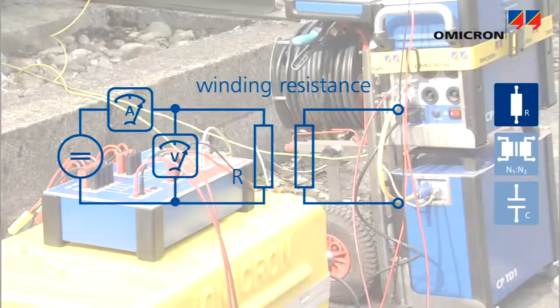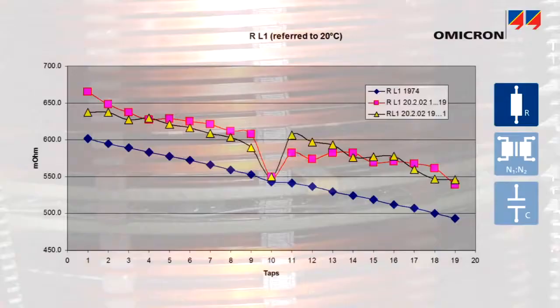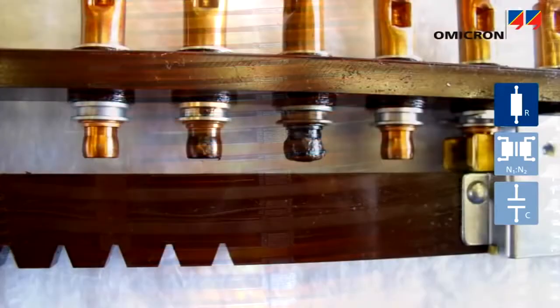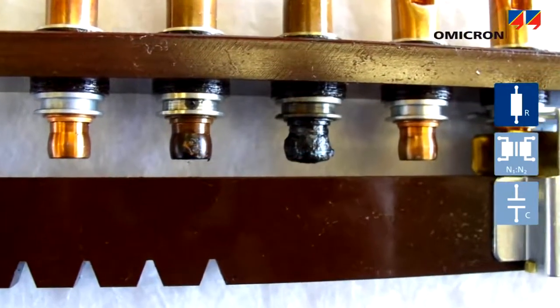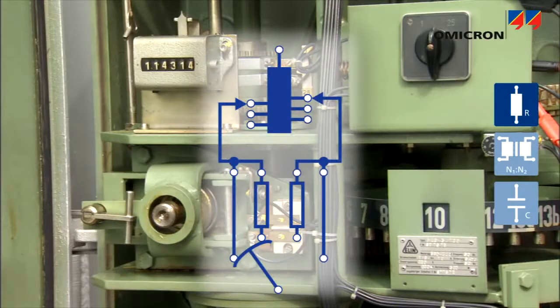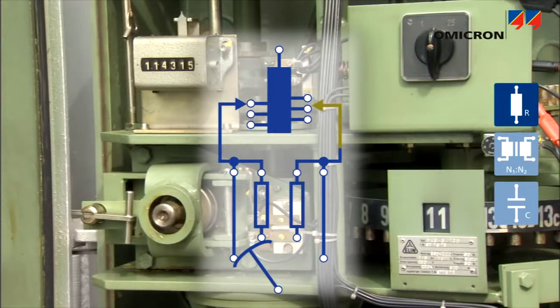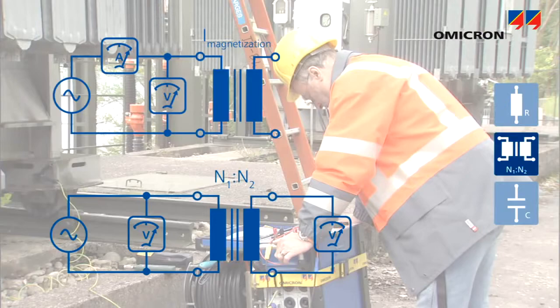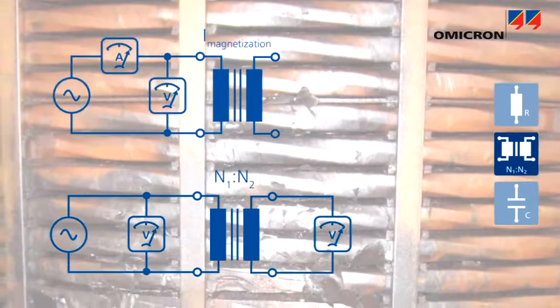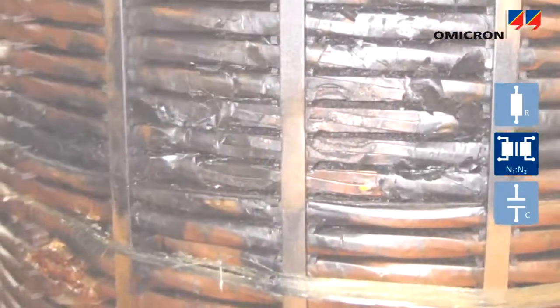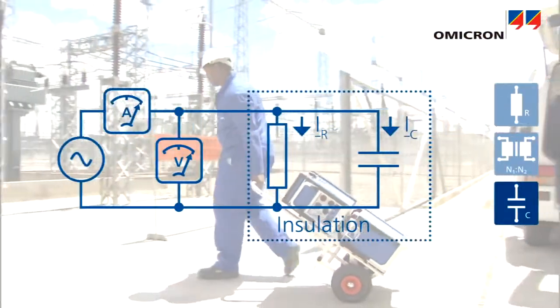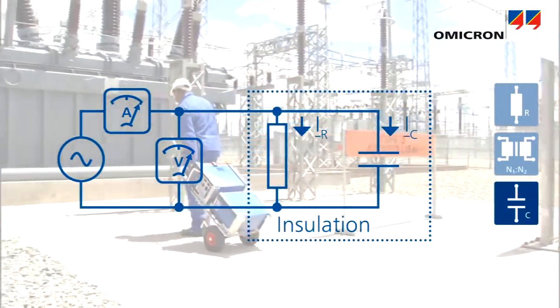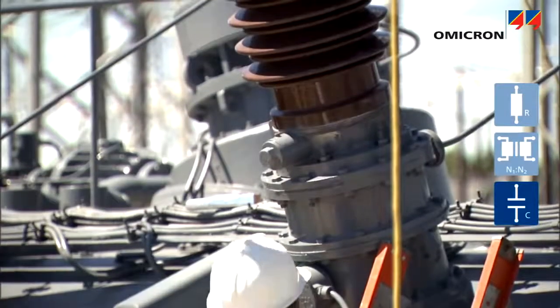Measuring the winding resistance and comparing it to factory measurements allows possible winding damage to be identified. For instance, winding short circuits or contact problems of the windings, leads, or the tap changer. Measuring ratio and magnetization current helps to identify short circuits between winding turns. Capacitance and dissipation factor or power factor measurements are performed to evaluate the condition of the transformer's bushings.